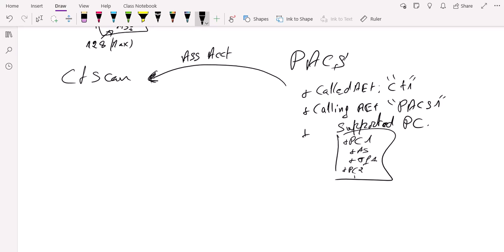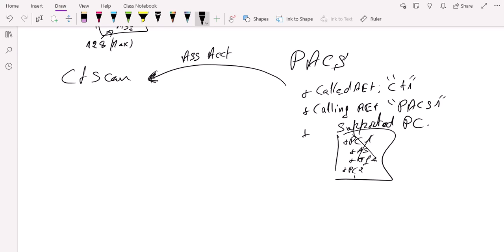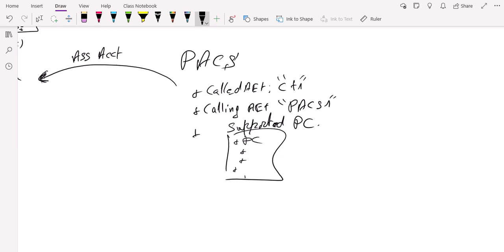If none of these presentation contexts were supported, you're going to just send an association reject. And then look, I'm sorry, I can't do actually any service. I can't help you. There is nothing in that list that I can do. And that's not really common. Because here the CT scan will know that this is a PACS and will expect that a PACS, that the basic function of a PACS is to archive and to store images. And the SCU or the CT scan won't ask a PACS about some services that is not supposed to use like worklist services, which is used by the modality systems. So that's why the exchange won't be possible until the two parts agree on the services or the functions that they would use and the way data is supposed to be transferred.